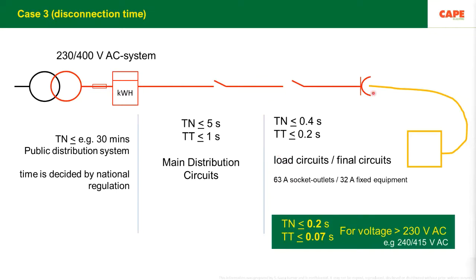For a fault, what I have shown here is a transformer. You have a meter, meaning your point of commencement of supply, your main distribution, where I am moving the cursor. Then you have your final distribution board. For final distribution boards, up to 63 amps socket outlets or up to 32 amps fixed electrical installation, the maximum allowed disconnection time is what is shown here: 0.4 seconds in case of a TN system, 0.2 seconds in case of a TT system. For the fixed electrical installation, the main distribution boards, the disconnection time is very simple: the tripping time of your MCB can go up to 5 seconds in case of a TN system and up to 1 second in case of a TT system.